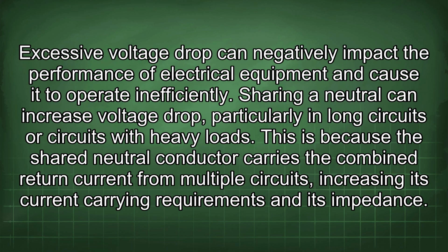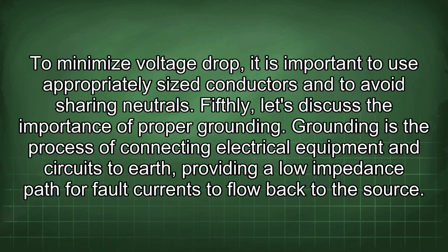Excessive voltage drop can negatively impact the performance of electrical equipment and cause it to operate inefficiently. Sharing a neutral can increase voltage drop, particularly in long circuits or circuits with heavy loads. This is because the shared neutral conductor carries the combined return current from multiple circuits, increasing its current carrying requirements and its impedance. To minimize voltage drop, it is important to use appropriately sized conductors and to avoid sharing neutrals.